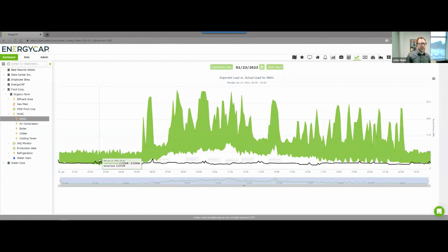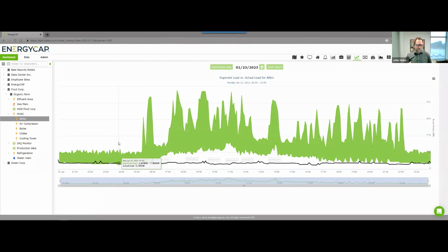This is the typical trend for this air handler unit. For some reason, on January 23rd, it just didn't function properly. That's why I have all these notifications, because it actually wasn't working. Even for this first notification, we could have sent this to an engineer or someone assigned to it, and they could go out and take a look at what's going on. So that's the use of the Sentinel matched up with notifications and alarms.